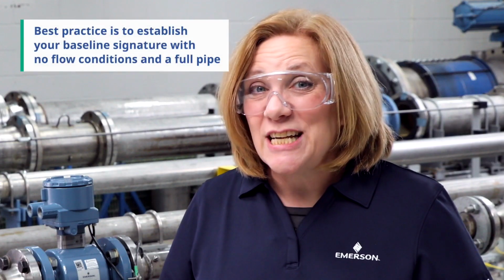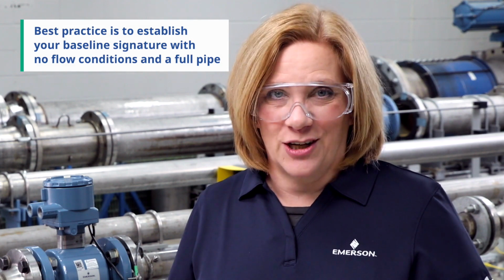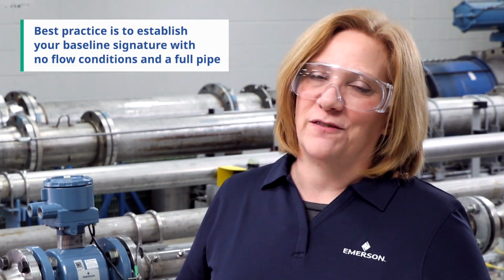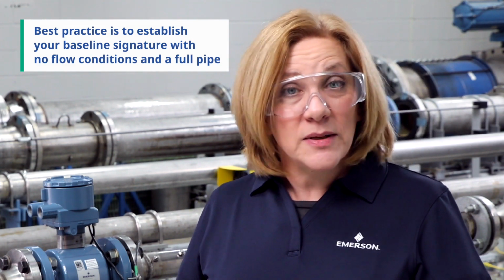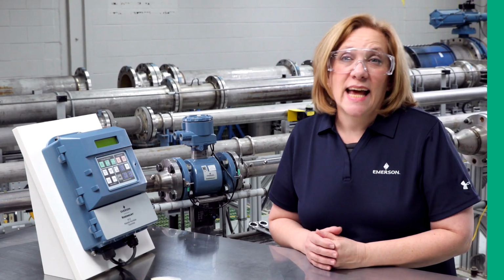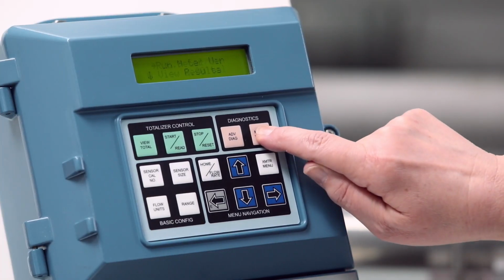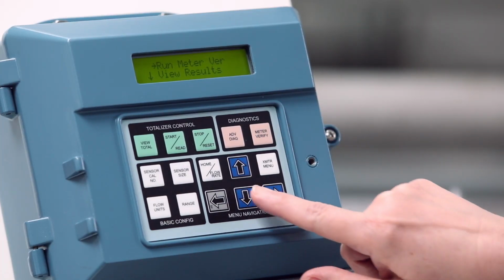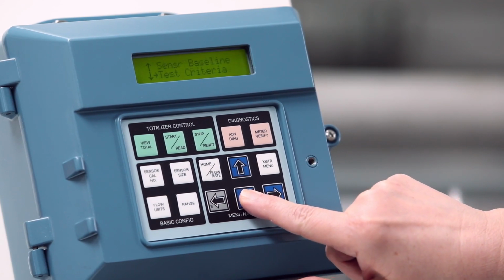Best practice is to establish your baseline signature with no flow conditions and a full pipe. If you are unable to get a no flow condition, you do have the option to set the test criteria for a full pipe flowing condition. To set the baseline signature, push the meter verify button. Then scroll down to test criteria and select your conditions.